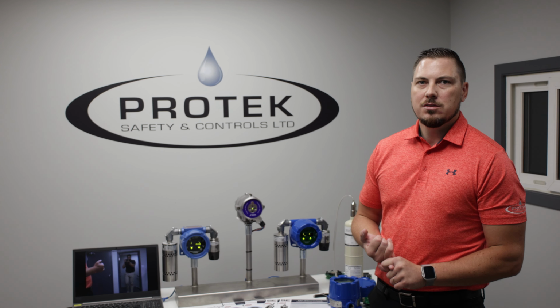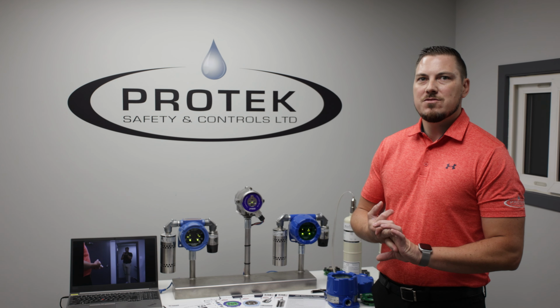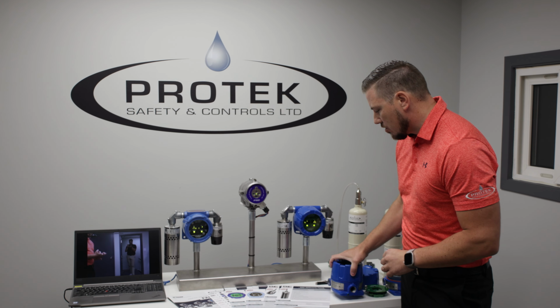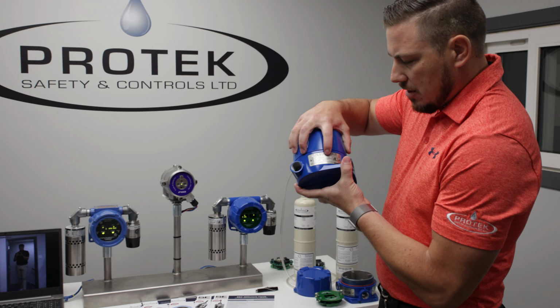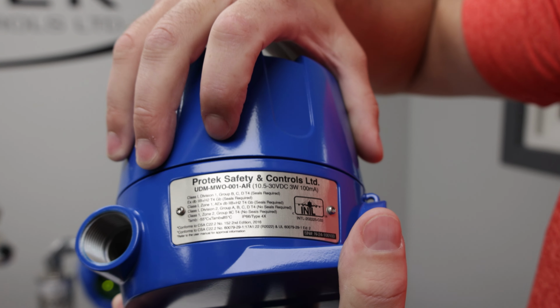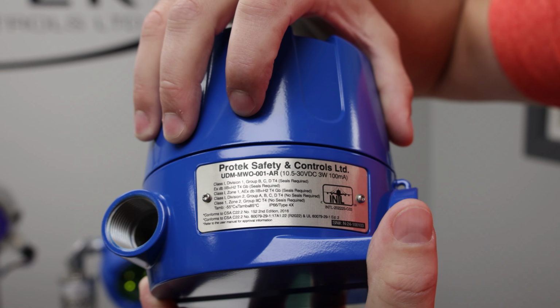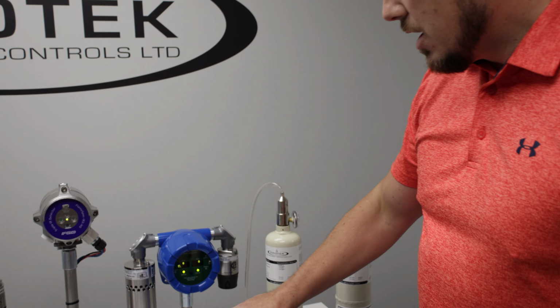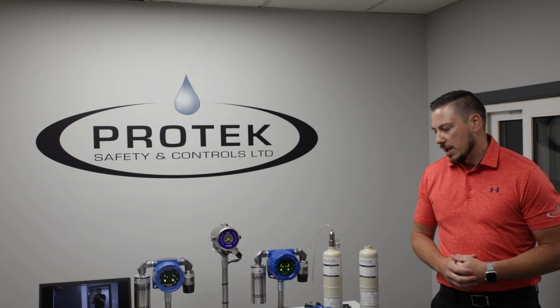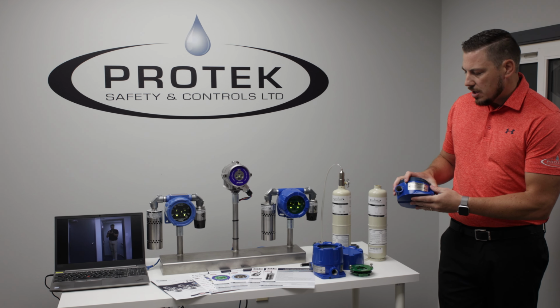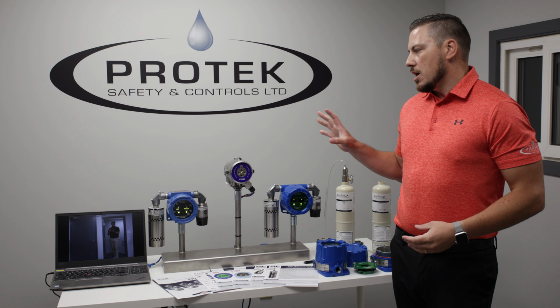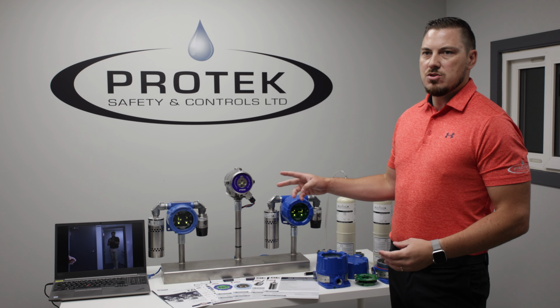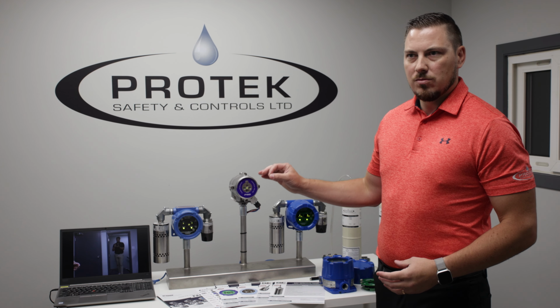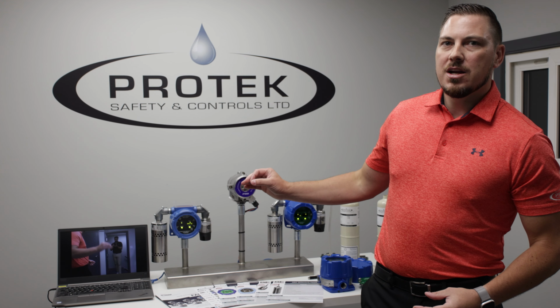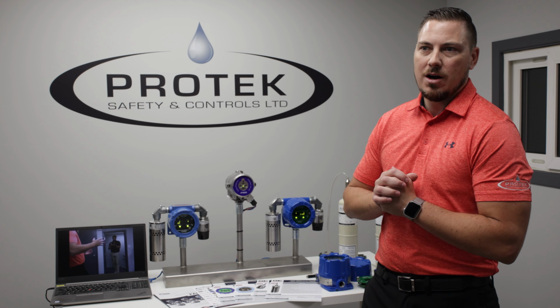One other thing we did was, we not only have Class 1 Div 1, Zone 1 certification, but we did Class 1 Div 2, no seals required. If you take a close look at the label here, it states Class 1 Div 1 seals required, Class 1 Div 2 no seals required. So when your electrical inspector sees that, he won't be questioning whether or not you have to put a seal on it. The same goes for our remote sensor separation kit here as well. If you are utilizing a UDM without the 4-wire, without the 2 and 3 wire retrofit solution, it is also Class 1 Div 1 certified and Class 1 Div 2 or Zone 2 no seals required as well.